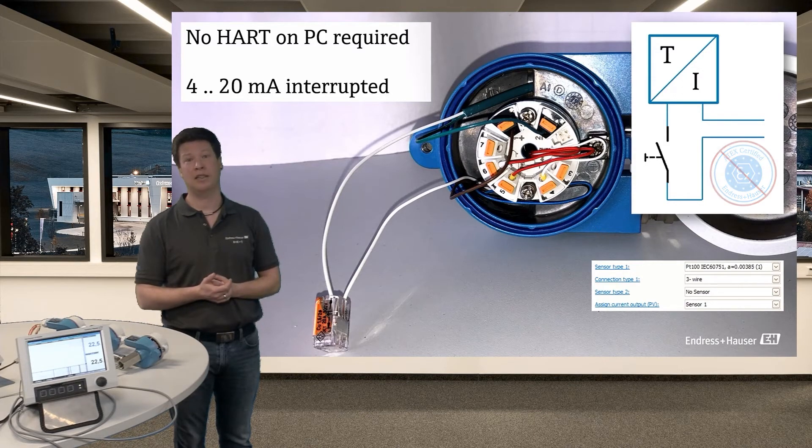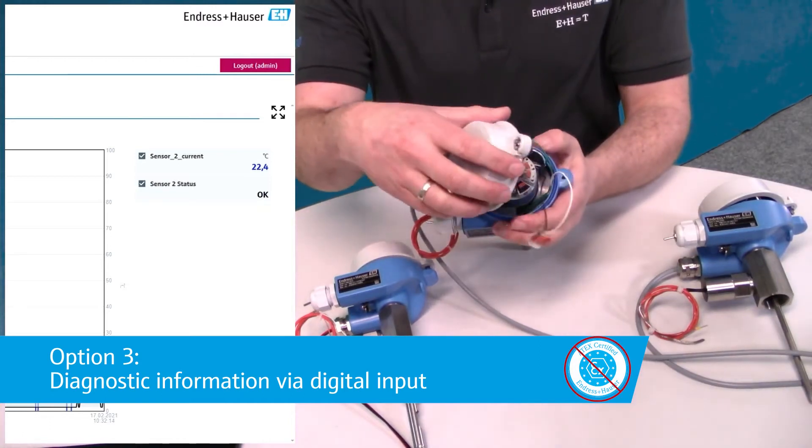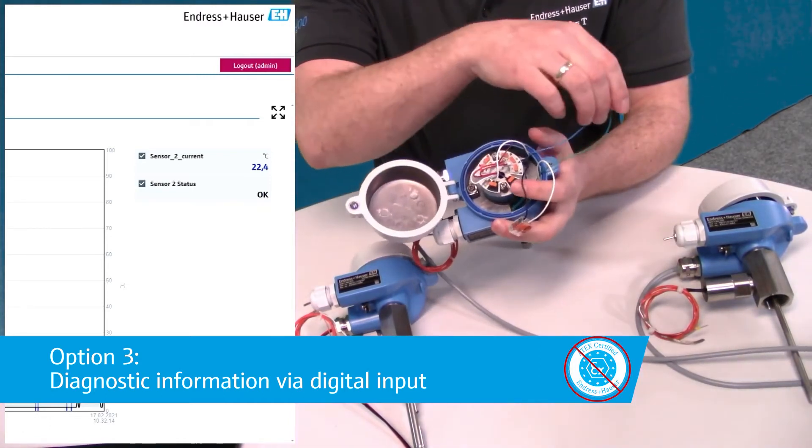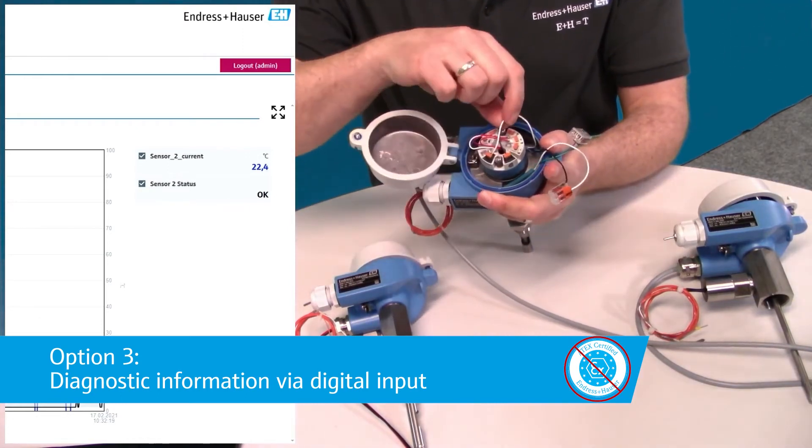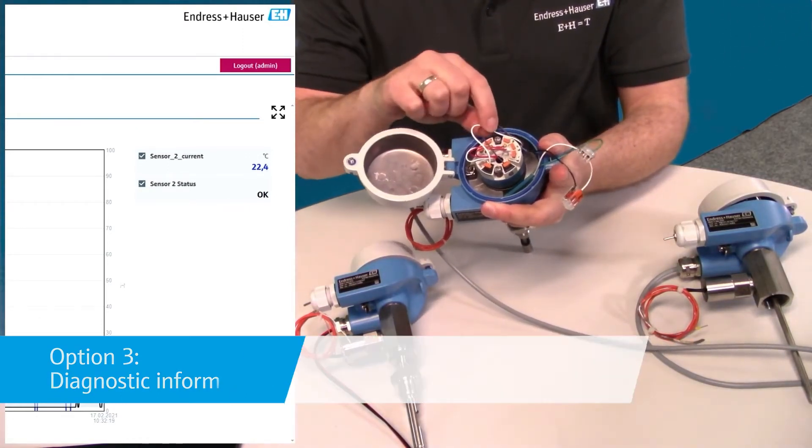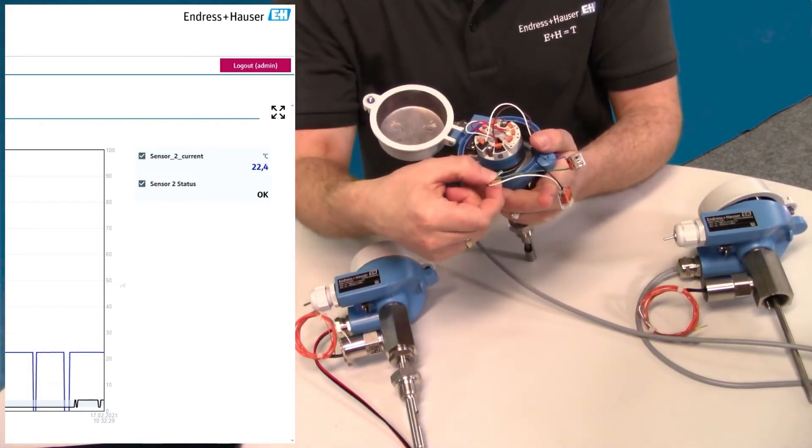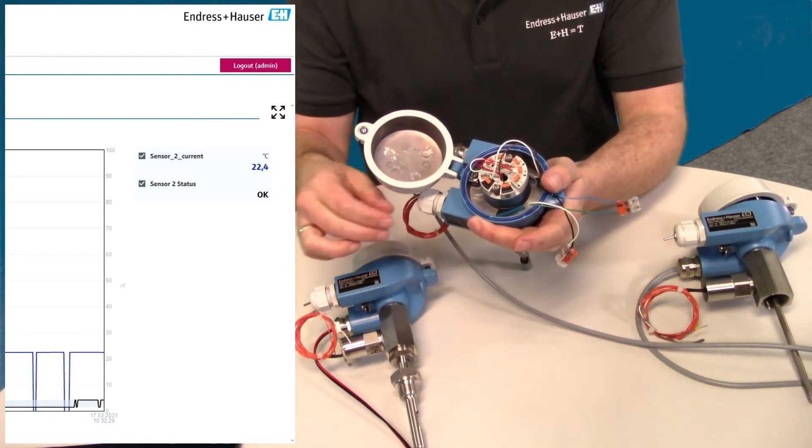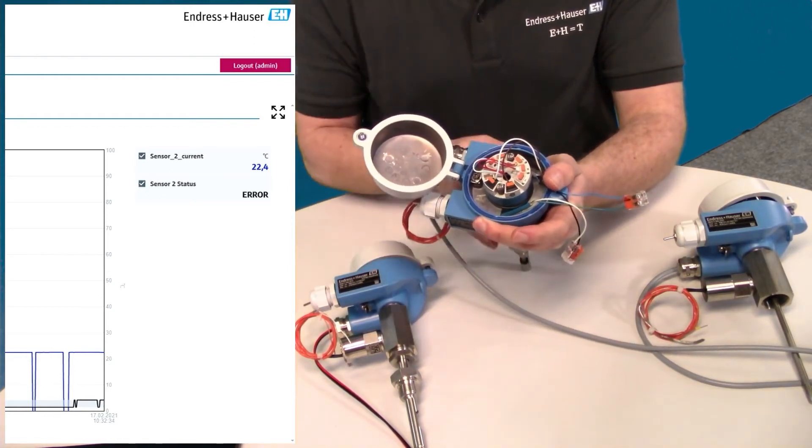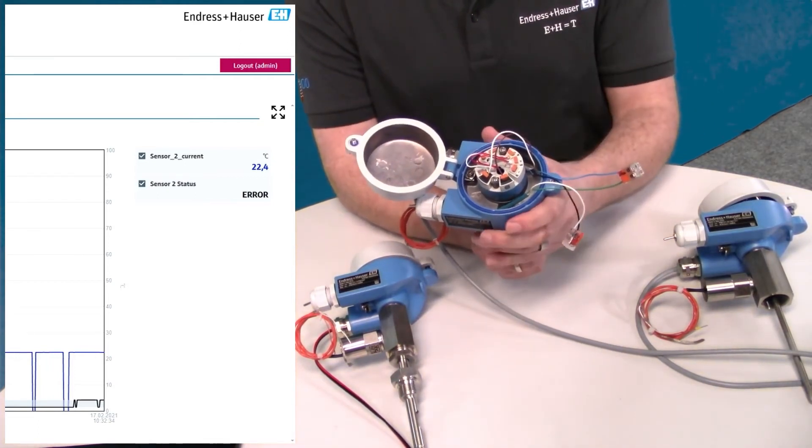Next option requires four wires from the PLC and a digital input. So now we have the 4 to 20 milliamp loop directly going to the PLC and two more wires going directly to the pressure switch. That means when the switch is activated the digital input on the PLC gets that warning signal.